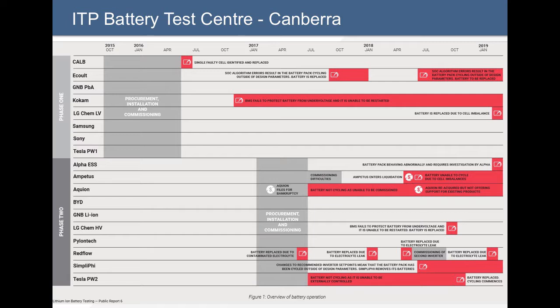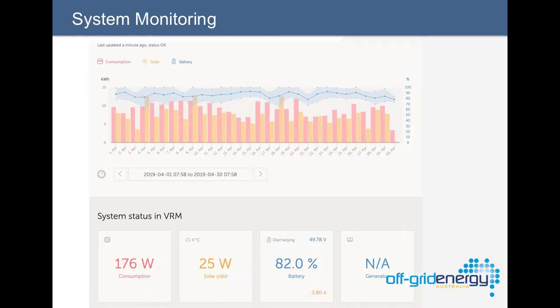They do sped-up testing, cycling the battery quickly so it replicates a 10-year period of operation. A lot of these batteries have a 10-year warranty, and they'll state that at the end of that period, or after a certain kilowatt hour throughput, the battery should retain 60% or 80% of its original capacity - that's around the range most lithium batteries are at. Some of the testing they've done reflects that that's where they'd expect it to be, based on their cycle testing.